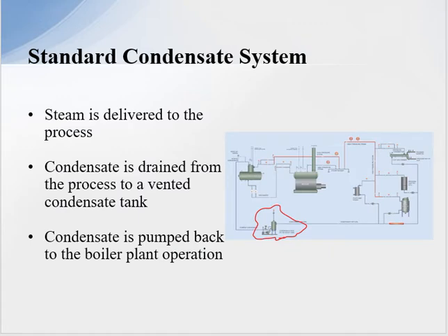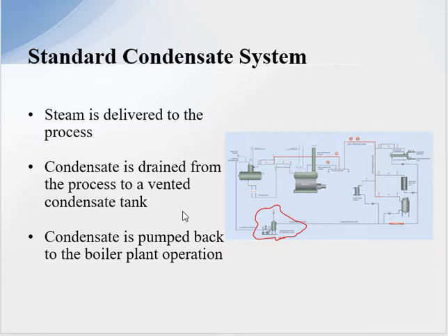As a standard condensate system, steam is given to the processes and then we come back to the condensate pump, which pumps back into the deaerator. This system does need a condensate pump to deliver the condensate back to the boiler plant. And when we put in an atmospheric tank system, we have to understand we're going to lose flash steam to the system.